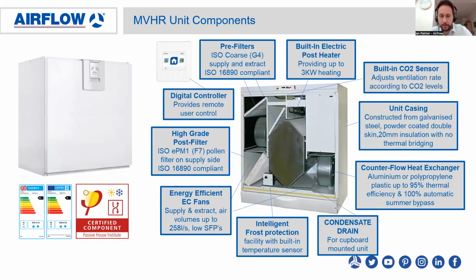The image right in the middle is the counter crossflow heat exchanger. This could be made of aluminium or polypropylene, and they tend to achieve heat recovery efficiencies up to 95%. Importantly, they also have a summer bypass to help with Part O overheating. It's an automatic system. It will bypass the heat recovery when the temperature's reached a certain point, so that it's not recovering the heat in the summertime, and it's just supplying fresh air into the dwelling. This gives a form of free cooling in the summer.